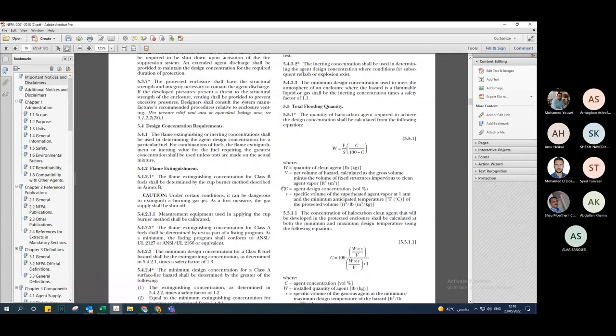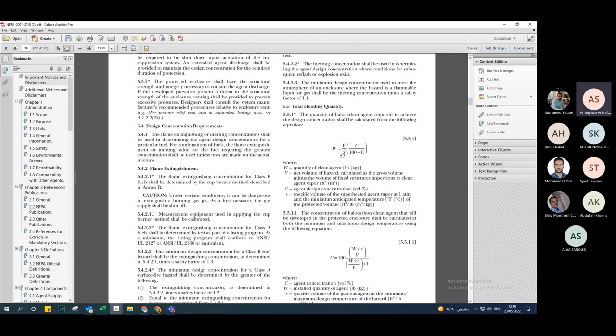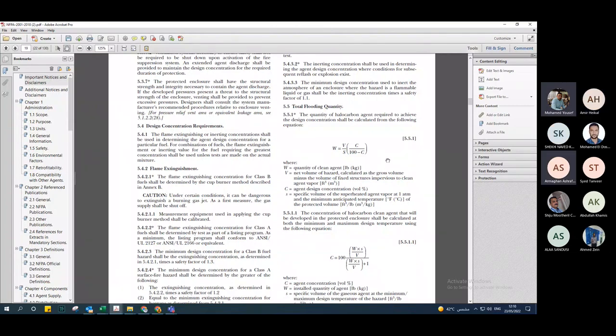So the equation is W = (V / S) × (C / (100 − C)). V is the volume, S is the specific volume, and C is the agent design concentration. We will explain what value to use for C.